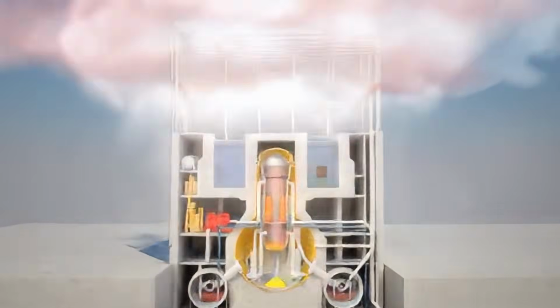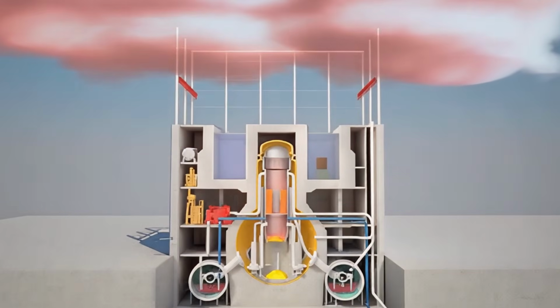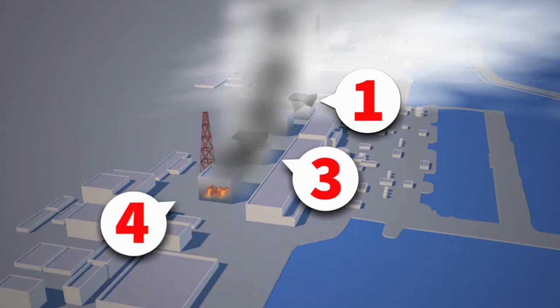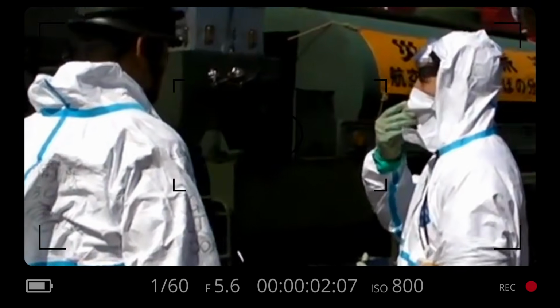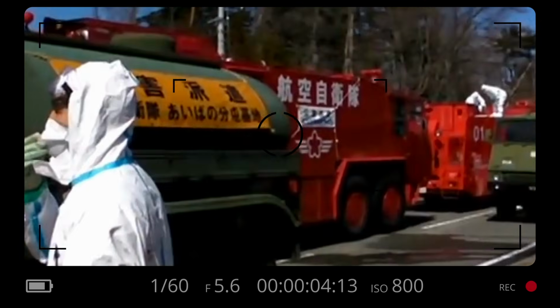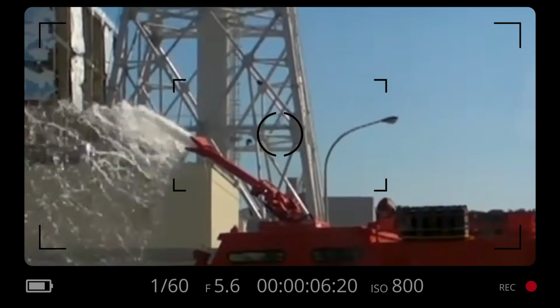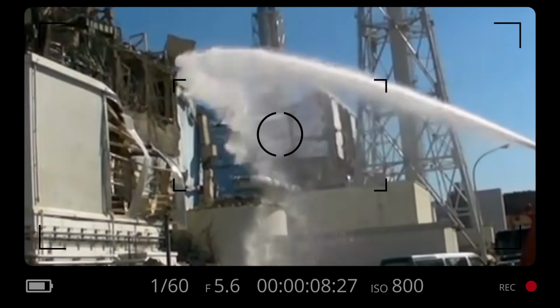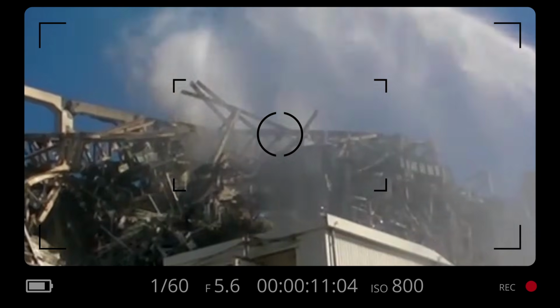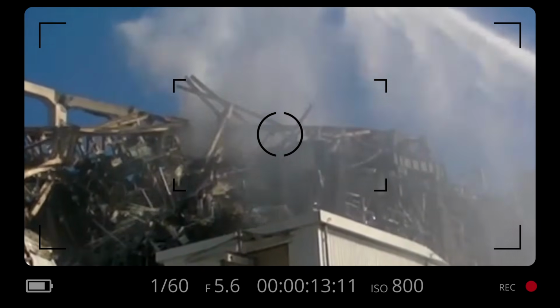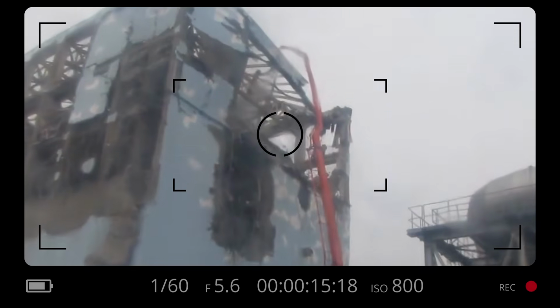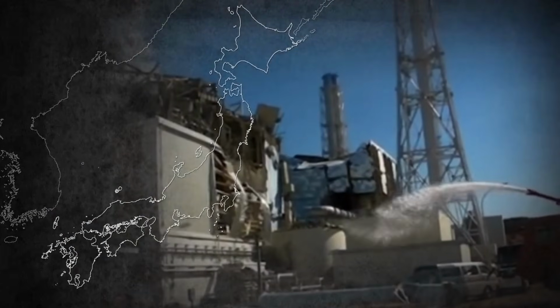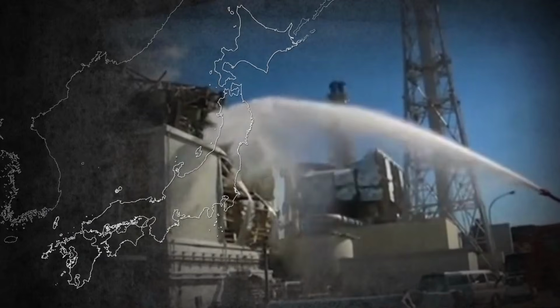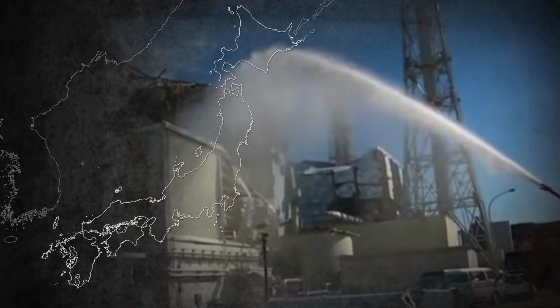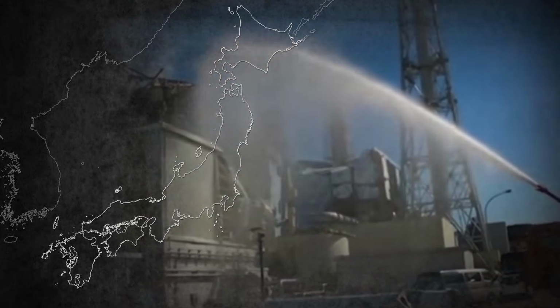On March 15th, the building of Unit 4 exploded, completely destroying the upper structure of the facility, and generating massive international dread regarding the actual condition of the pool. Firefighters began to inject seawater utilizing improvised pumping equipment, and later military helicopters and water cannons were deployed to drop water directly over the fuel pools. Fortunately, with the passing of days, they managed to successfully re-establish a continuous water injection and stabilize the overall temperature of the pool. Units 5 and 6 were able to maintain sufficient cooling until reaching a cold shutdown state, thanks to the fact that both units preserved a functional diesel generator, situated in a higher and more protected area.